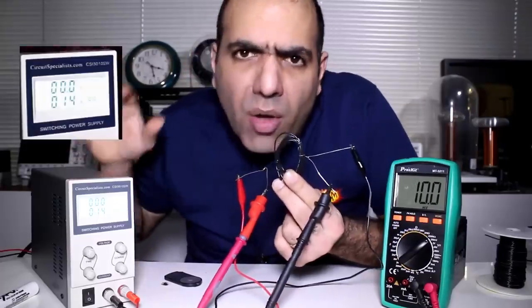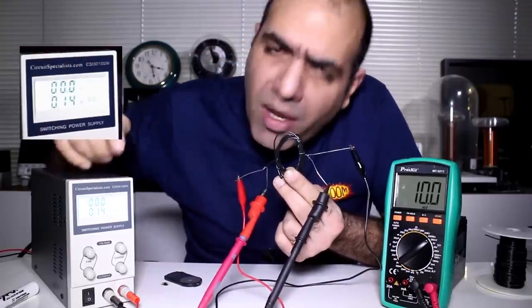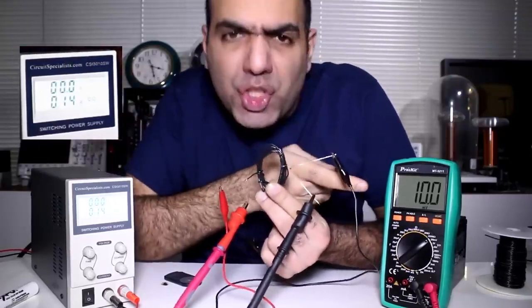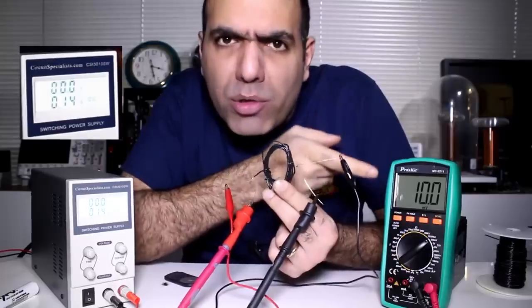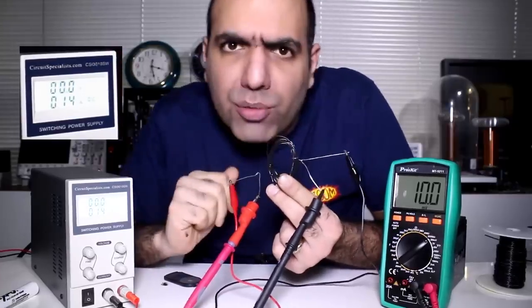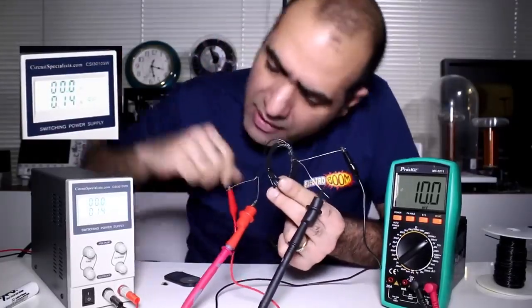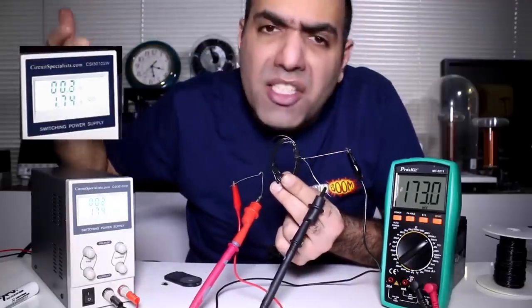I set the current to 100 milliamps and you can see that the supply can't show it accurately, but the shunt can. That 10 millivolt voltage times 10 is the current running through the shunt, which is 100 milliamps. And if I change the current, our reading is still pretty accurate.